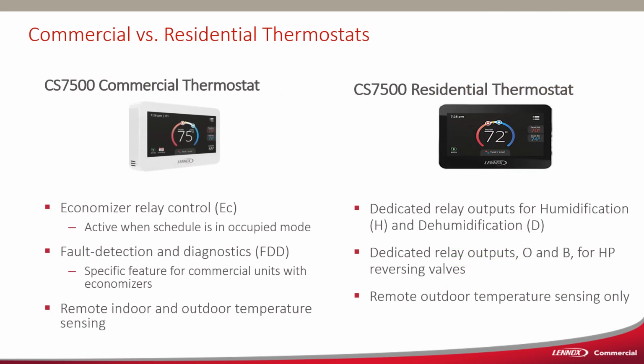With the ComfortSense 7500 thermostat, you've got to be careful because there's also a residential version of the ComfortSense 7500, and they are not the same. Typical of a commercial thermostat, it's got an economizer relay based on the scheduled occupancy of the building that's going to control our motorized outside air damper or economizer. The residential stat does not have that. Fault detection and diagnostics, the residential stat does not have that either. And remote indoor and outdoor temperature sensing, whereas the residential stat just has remote outdoor temperature sensing.